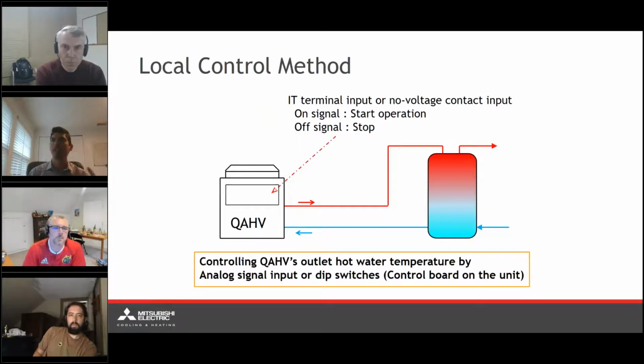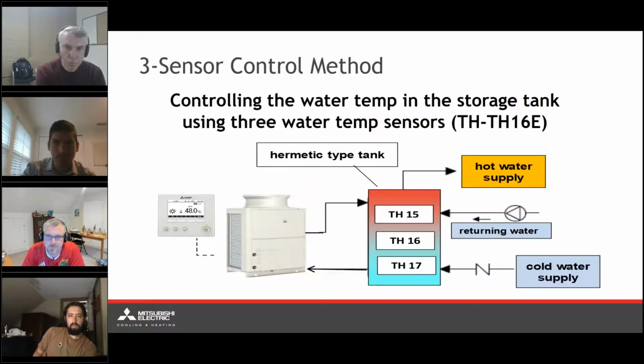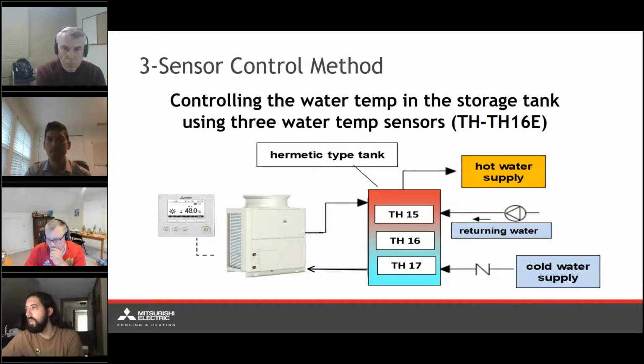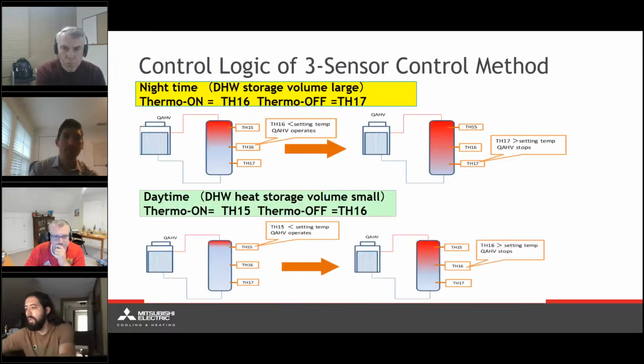Here's the local control, targeting the outlet water temperature for this instance, which is feeding into a semi-hermetic storage tank. We have the 3 sensor control. This is similar to what we just saw previously. The temperature sensors are located at the top, middle, and bottom of the tank. Just based on gravity within the tank itself, we're going to be getting 3 separate temperature readings. It's going to be hotter water towards the top of the tank, colder water towards the bottom. But from an actual control logic standpoint, this is what we're going to be looking at in the system.